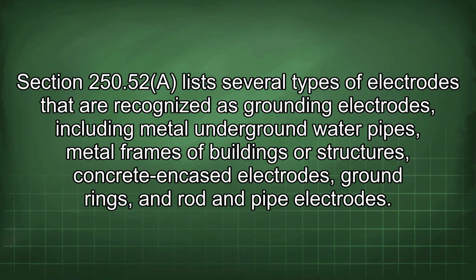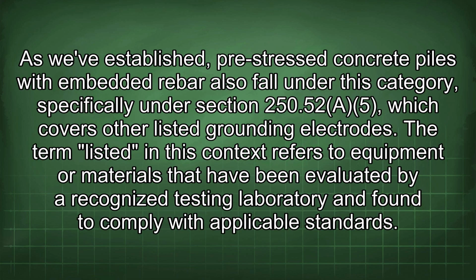Section 250.52 lists several types of electrodes that are recognized as grounding electrodes, including metal underground water pipes, metal frames of buildings or structures, concrete encased electrodes, ground rings, and rod and pipe electrodes. As we've established, pre-stressed concrete piles with embedded rebar also fall under this category, specifically under Section 250.52(A)(5), which covers other listed grounding electrodes. The term listed in this context refers to equipment or materials that have been evaluated by a recognized testing laboratory and found to comply with applicable standards.